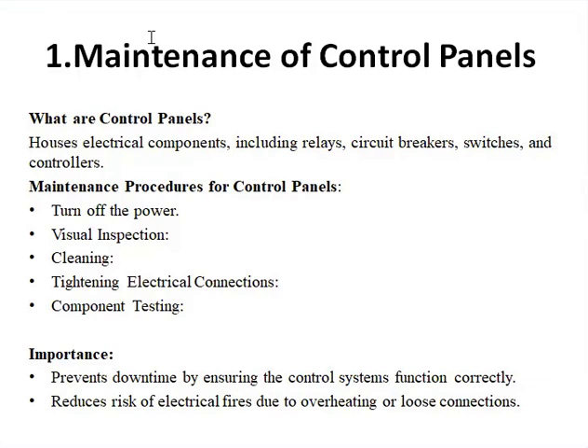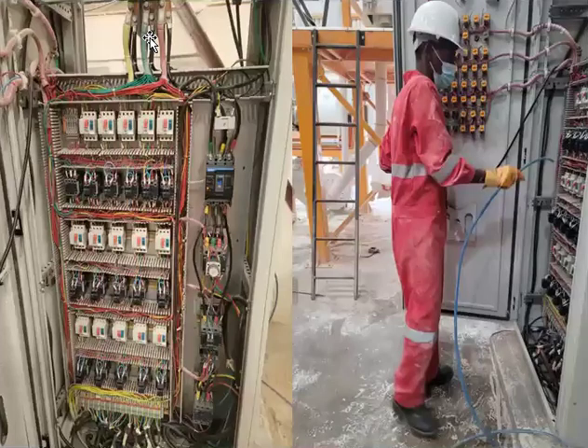So there is cleaning. Cleaning is essential in maintenance, and most people overlook it. If these circuit breakers, contactors, overloads, and timers are not cleaned, they connect themselves, like they are connected by electromagnetic induction. So if there is a lot of dust in between, you find when the contactor gets interlocked, it fails to come back. Or when the circuit breaker trips, it will fail to come back. Sometimes you may think the circuit breaker has tripped, yet it has not tripped due to dust. And also dust in these connectors makes them loose.